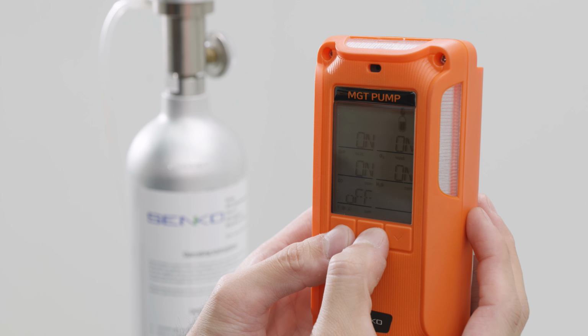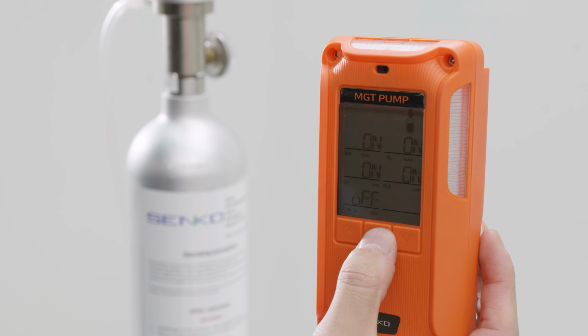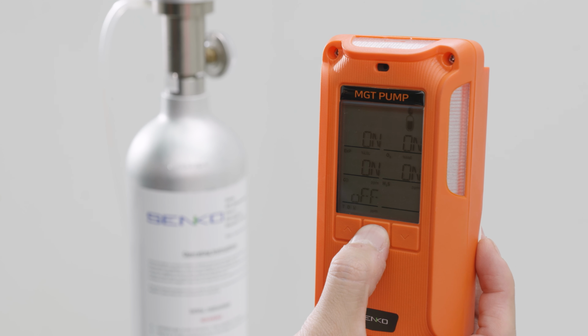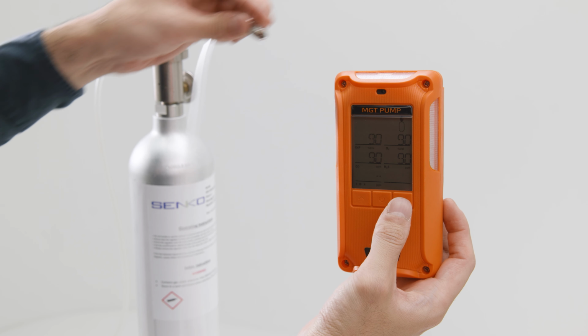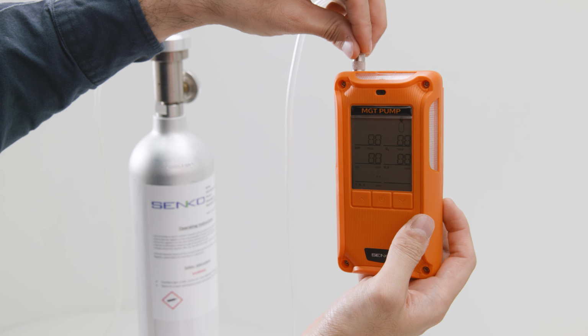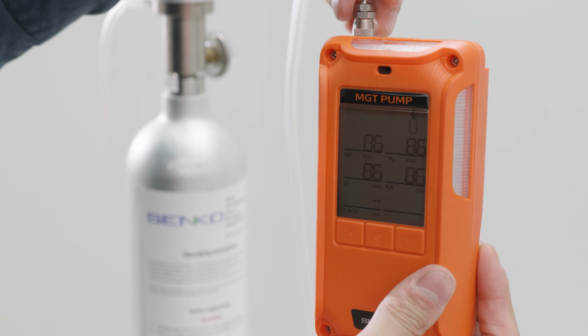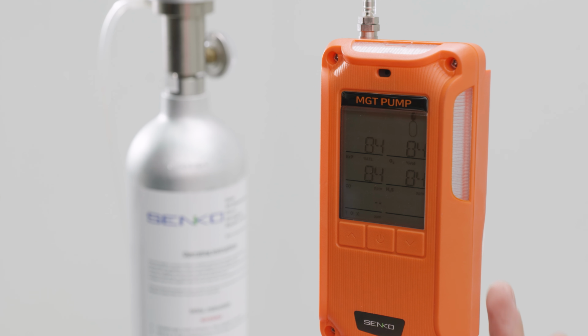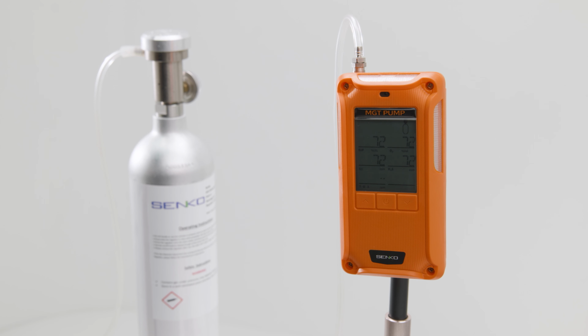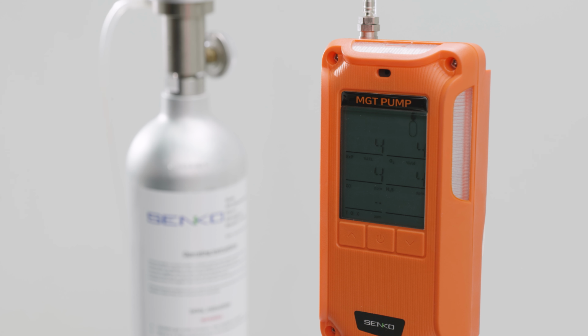Then, in the span run screen, select the target sensors and set them on or off. To start span calibration, press and hold the Select button to begin the process automatically. Once the calibration starts, slowly open the regulator to apply the standard calibration gas. A countdown of approximately 90 to 180 seconds is performed, and when it is complete, the result is displayed as OK or FA.